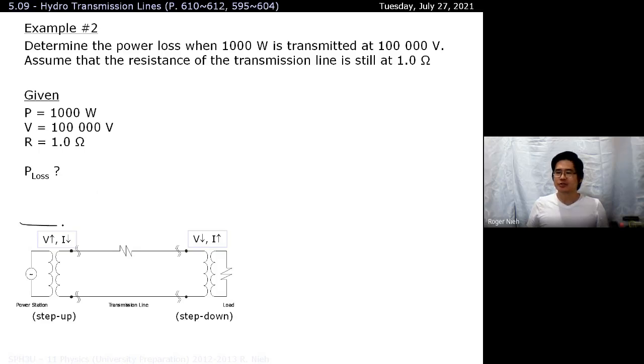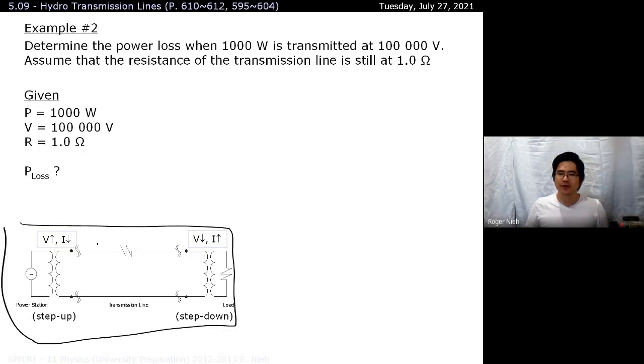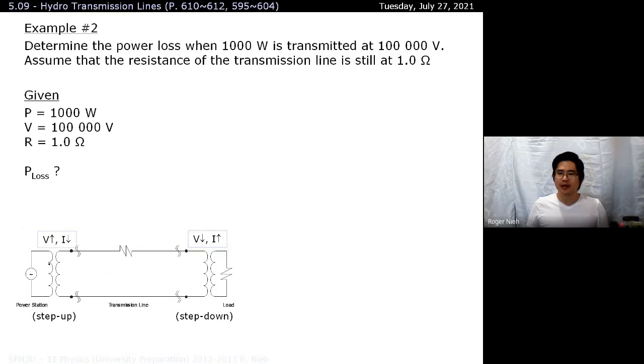Let's use this super simplified example to show you how much more efficient this setup is. I didn't give you too much information, I just said we started off with 1,000 watts, and we're going to bring up the voltage to something incredibly high. Let's say we bring it up to 100,000 volts. In the past we only had it at 100 volts, so now we increase the voltage by 1,000 times. As a consequence, when the voltage goes up 1,000 times, the current has to drop by 1,000 times as well. In the previous example we had 10 amperes of current. Let's do the math right now, and you'll see it still correlates.